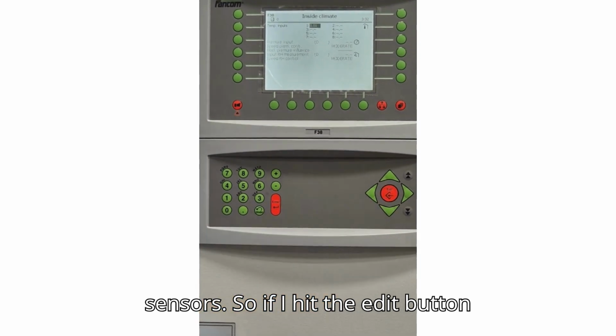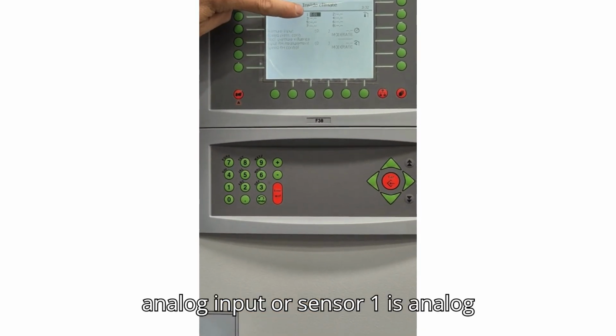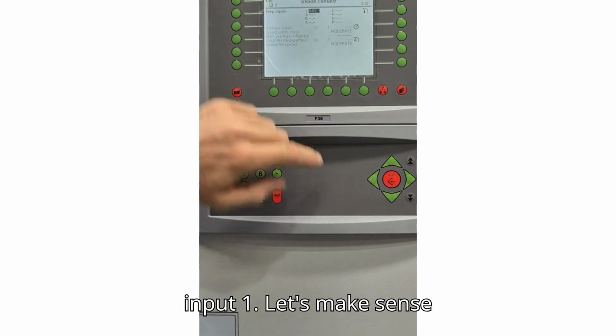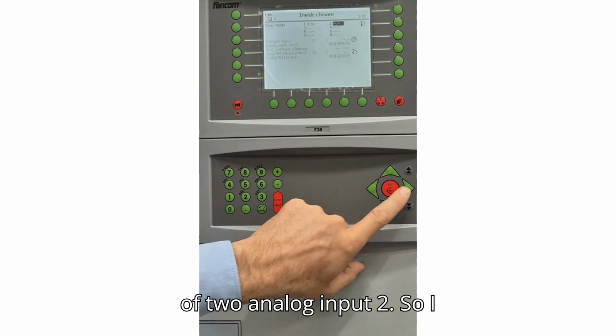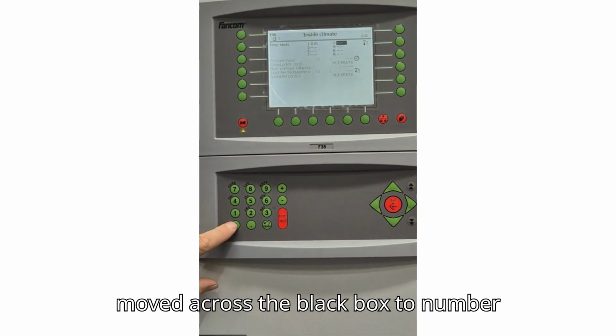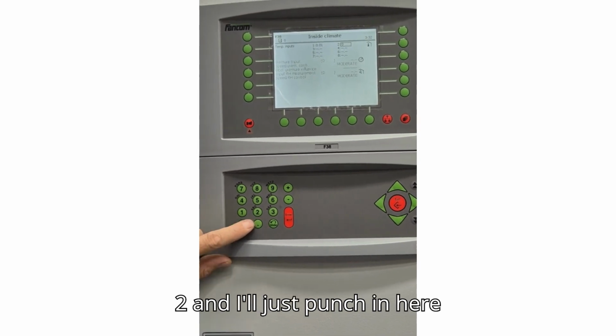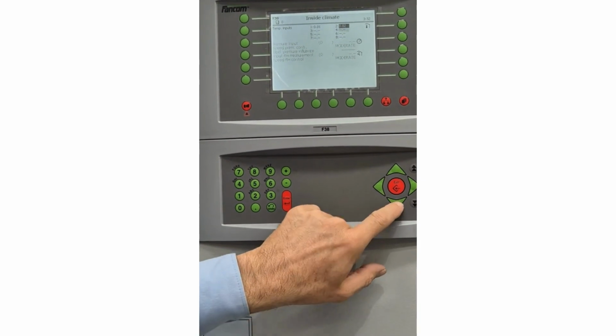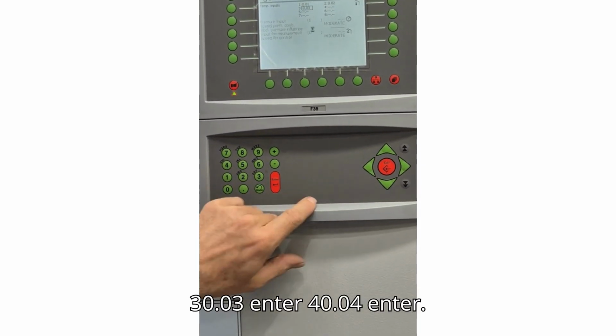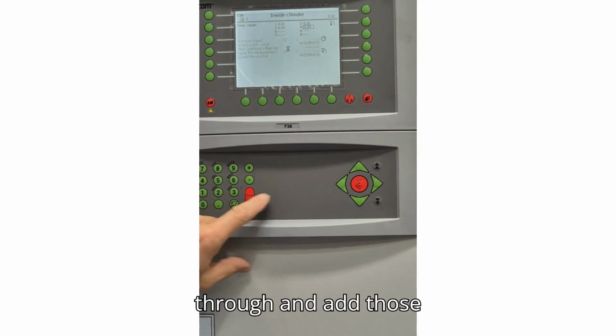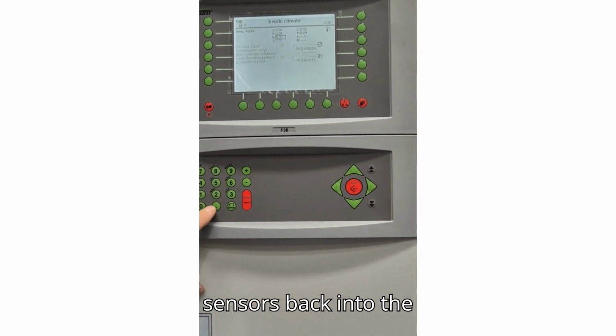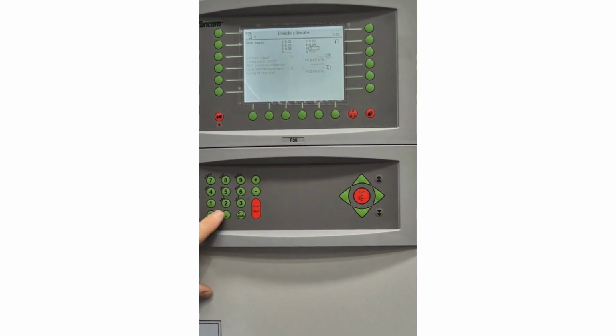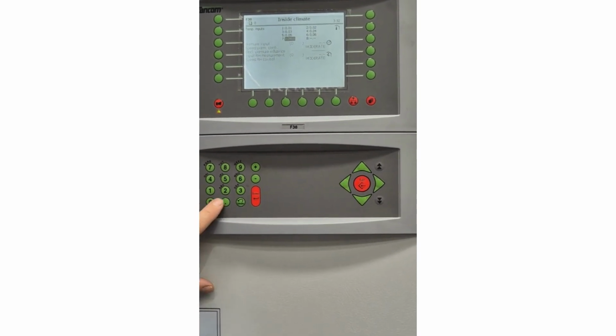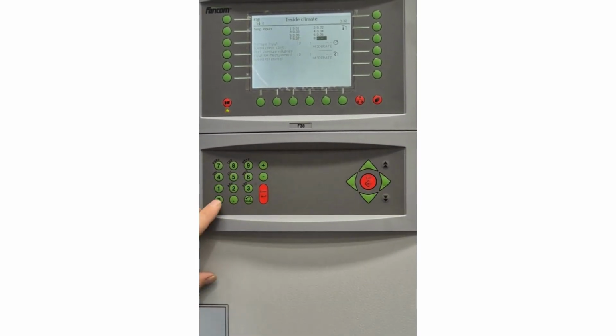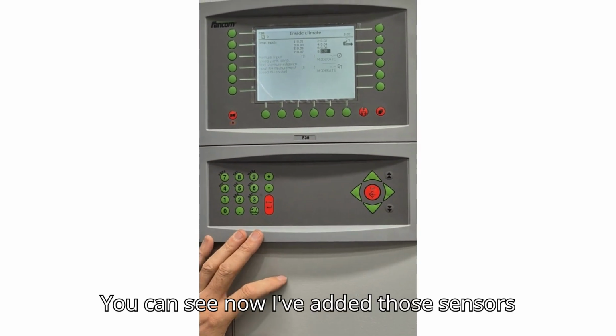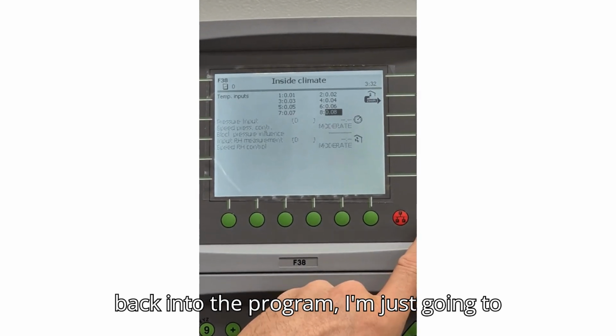So if I hit the edit button once, we're on analog input, or sensor 1 is analog input 1. Let's make sensor 2 analog input 2. So I moved across the black box to number 2, and I'll just punch in here 0.02, enter. I'll go across to 3, 0.03, enter. 4, 0.04, enter. I'm going to go through and add those sensors back into the program. You can see now I've added those sensors back into the program.